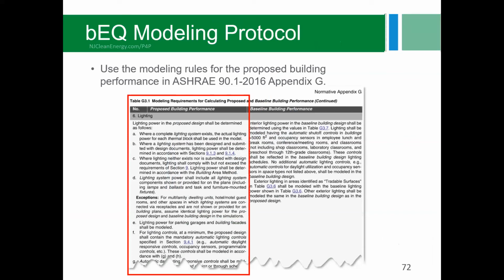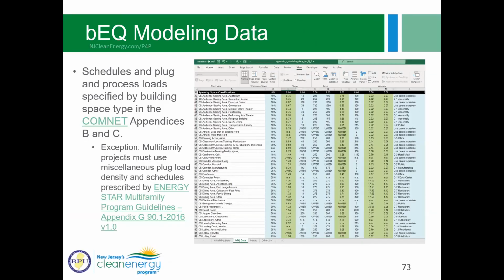So if you have things like an area where lighting is yet to be designed, and you say, well, I don't know what to put there, it's not designed, well, you would consult table G3.1 for how to treat that in your bEQ model. In terms of modeling data, you would use the schedules, plug and process loads specified by ComNet in appendices B and C. The exception would be for multifamily, where you would use the multifamily new construction program guidelines.